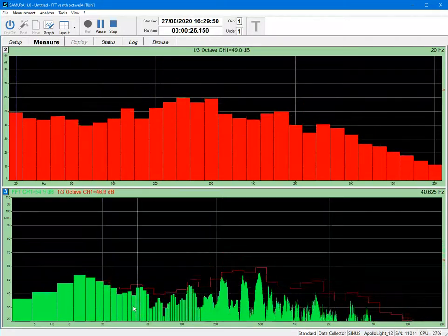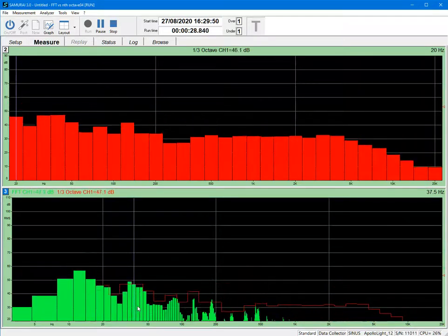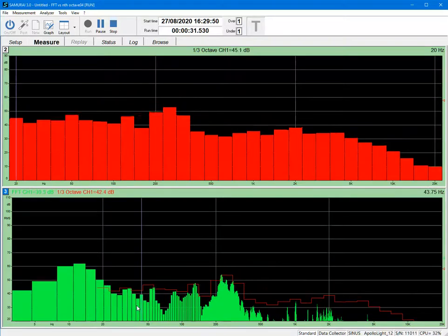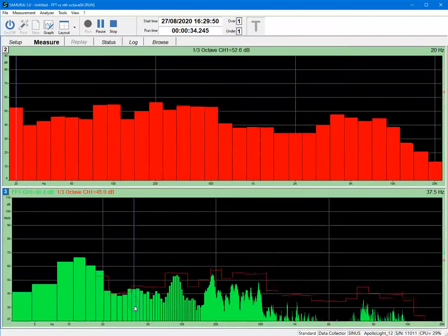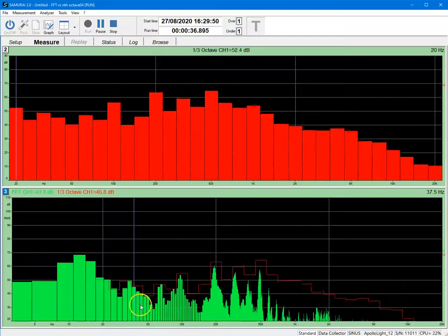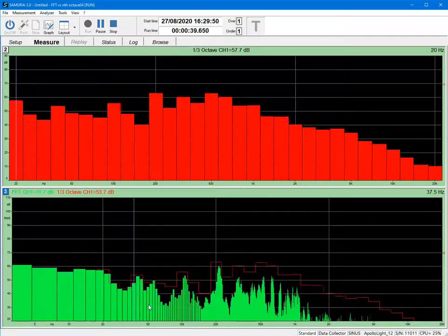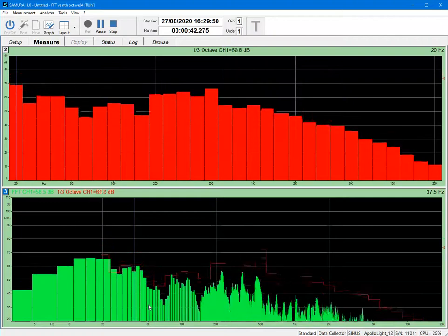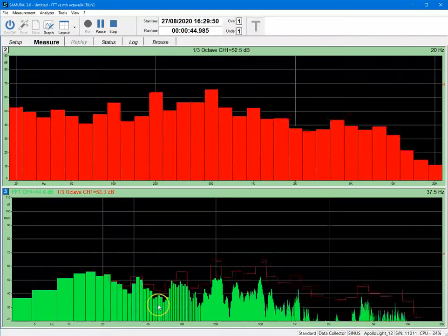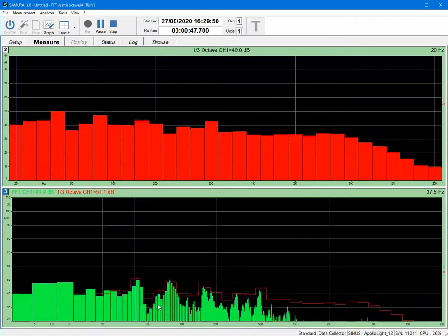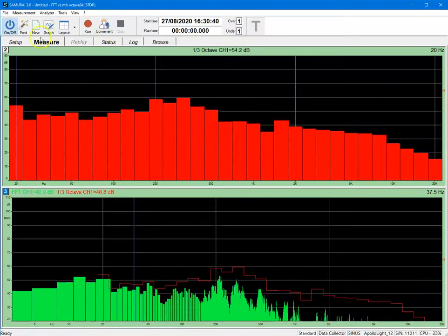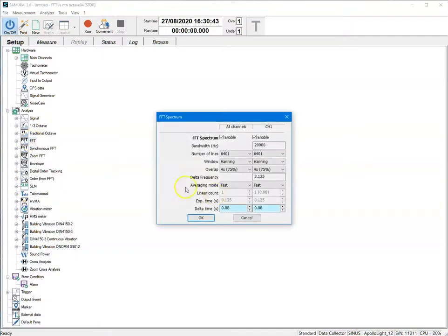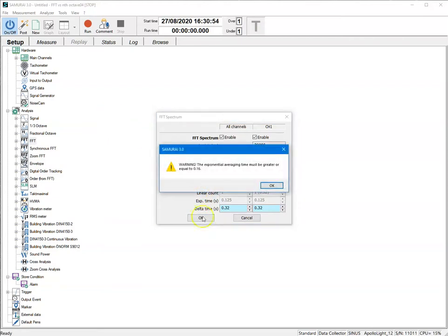Maybe I can do it accurately at 30 Hz. I've got 3 third octave bands there that I can synthesize. Still not strictly speaking enough. So even with 6,400 lines up to 20 kilohertz, I still can't really synthesize the 63 Hz band properly. Well, you could take this to a logical conclusion and say, well, let's take even more lines. And this obviously requires more CPU power to do the calculation. You won't have this kind of resolution on a portable device typically.